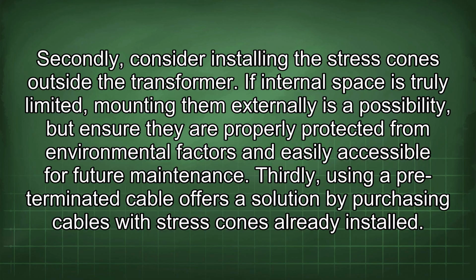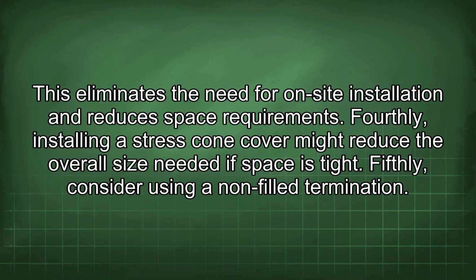Thirdly, using a pre-terminated cable offers a solution by purchasing cables with stress cones already installed. This eliminates the need for on-site installation and reduces space requirements. Fourthly, installing a stress cone cover might reduce the overall size needed if space is tight. Fifthly, consider using a non-filled termination.